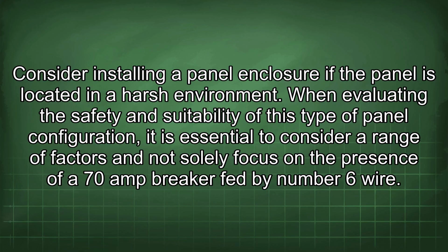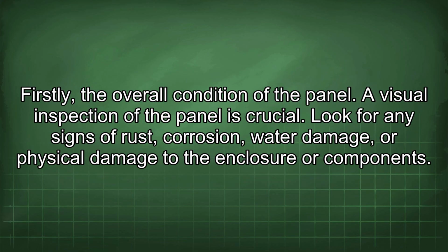When evaluating the safety and suitability of this type of panel configuration, it is essential to consider a range of factors and not solely focus on the presence of a 70-amp breaker fed by number 6 wire. Firstly, the overall condition of the panel. A visual inspection of the panel is crucial.